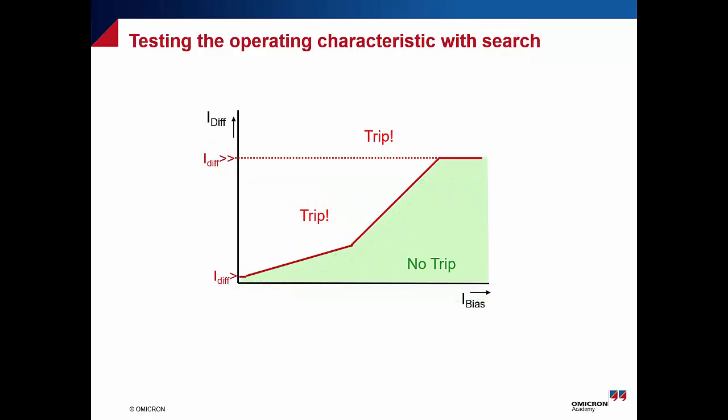Then the second technique, we call it search. If you have tested distance protection before, we also have shot and search. The search will look like that. As you see here, if you select the point line, it will go up and down until getting the maximum accurate point, which should be allocated on the line within the tolerance. And we need to apply at least two points for each line slope to verify whether that slope is correct as we set it or not. This is how it works in the search technique. And if it is within the tolerance, it should pass.